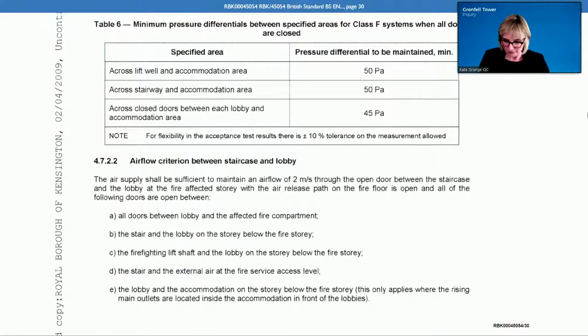Now, it follows from that, and it's consistent with the commissioning report, that there is, in fact, no record of what the door opening force was in the commissioning reports. That's right, isn't it? You're probably correct. Now, without some readings of door opening forces in the commissioning report, how could you be satisfied that the system met the requirement that the opening force on the door would not exceed 100 newtons, as set out in the British Standard, as identified as a criteria in PSB's technical submission?